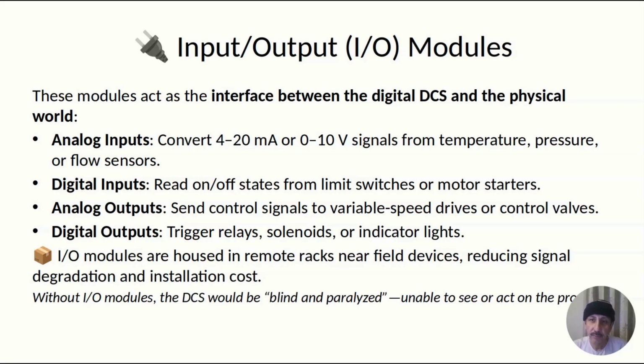Without them, the system would be completely disconnected from the process, unable to see what's happening or take any action. On the input side, we have two main types. Analog inputs handle continuous signals, most commonly the industrial standard 4 to 20 milliamp current loop, or sometimes 0 to 10 voltage signals. These come from devices like temperature transmitters, pressure gauges, or flow meters.